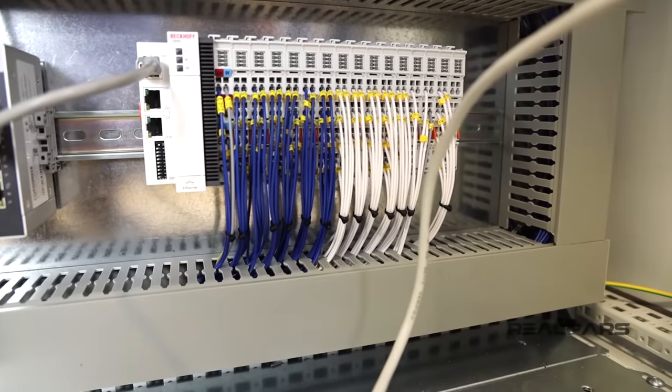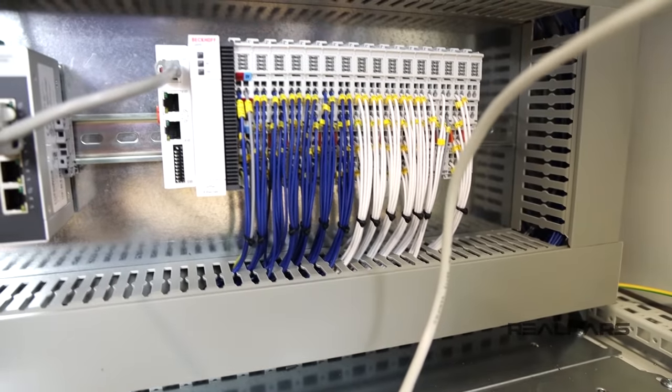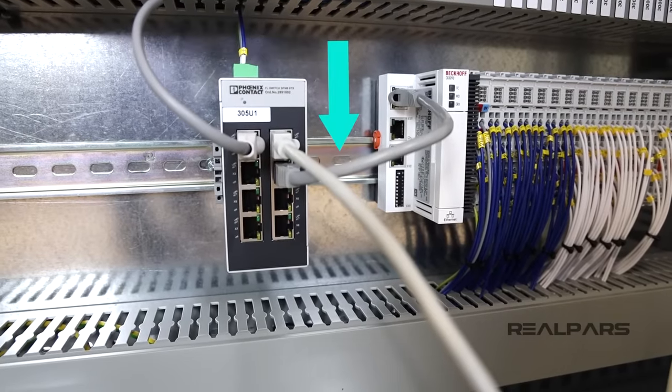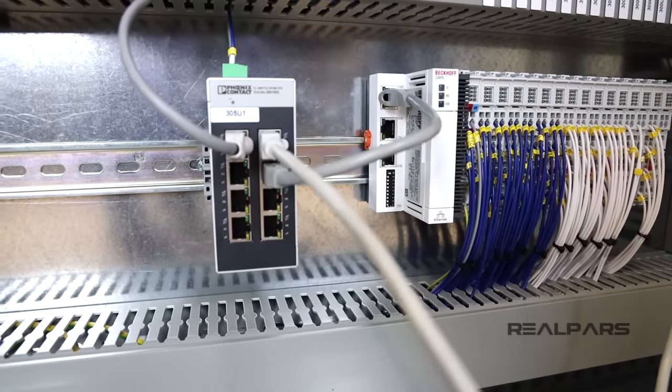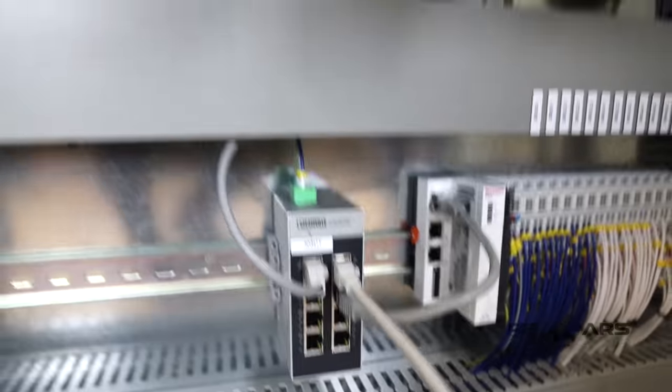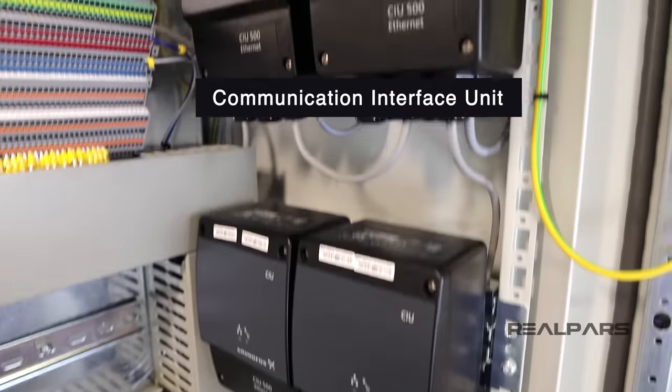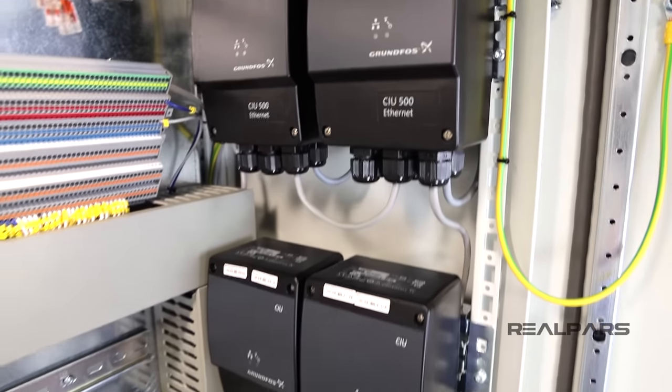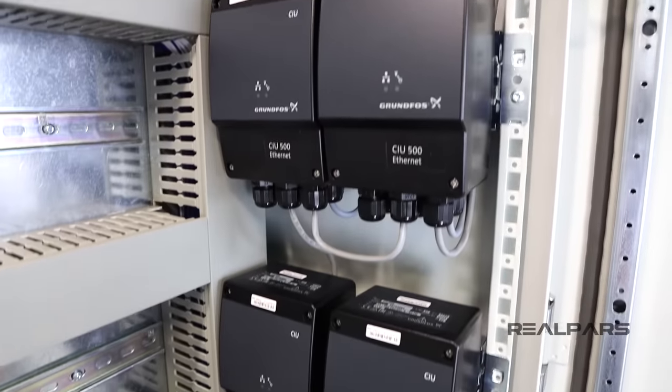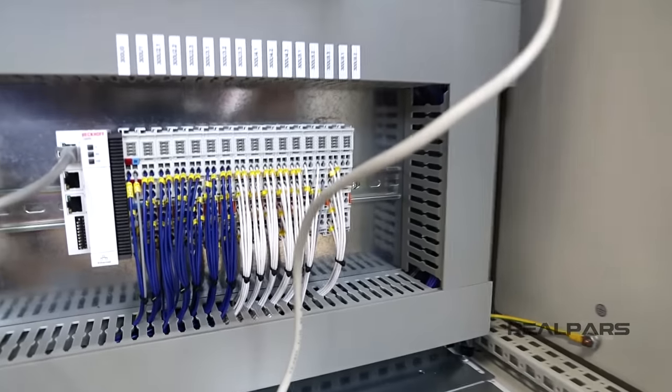Moving on, as you can see, the PLC is connected to an Ethernet switch via these cables. From the other end, the Ethernet switch is connected to these devices, which we call Communication Interface Unit or CIU. These interface units connect to the pumps that are installed in the field, and that's how the PLC can control the pumps.